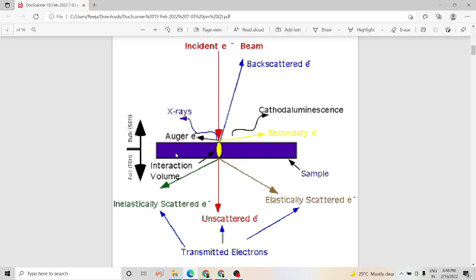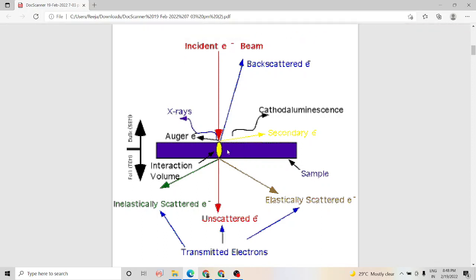As shown in a schematic diagram, when the incident electron beam falls on a sample, the different kinds of emissions possible are secondary electron emission, backscattered electron emission, x-ray emission, cathodoluminescence, and Auger electron emission. When the incident beam transmits through the sample, it can come out as unscattered, elastically scattered, or inelastically scattered electrons — all of which are detected in a transmission electron microscope for imaging.